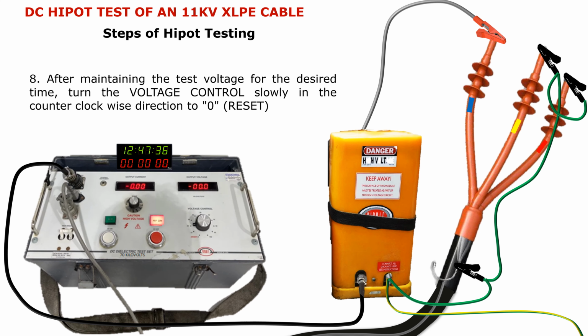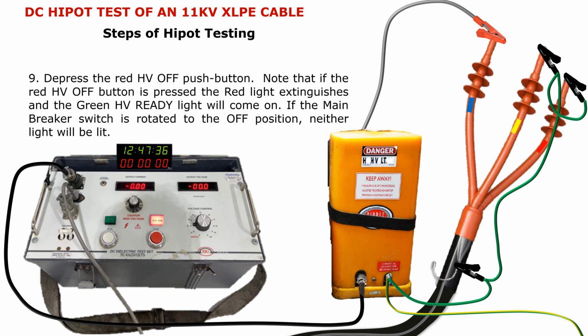After maintaining the test voltage for the desired time, turn the voltage control slowly in the counterclockwise direction to 0. Depress the red HV off push button. Note that if the red HV off button is pressed, the red light extinguishes and the green HV ready light will come on. If the main breaker switch is rotated to the off position, neither light will be lit.